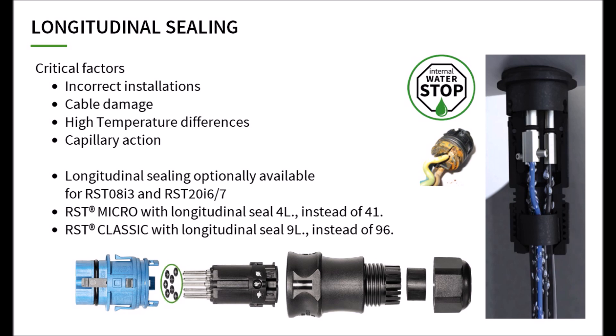In order to prevent the transmission of moisture through the cable system or the penetration of moisture into devices, RST connectors can optionally be supplied with contact seals to achieve longitudinal sealing. Components with longitudinal seals are identified by an L in the second digit of the article number. Longitudinal seals may only be used on one side of the plug connection, in male or in female connector.